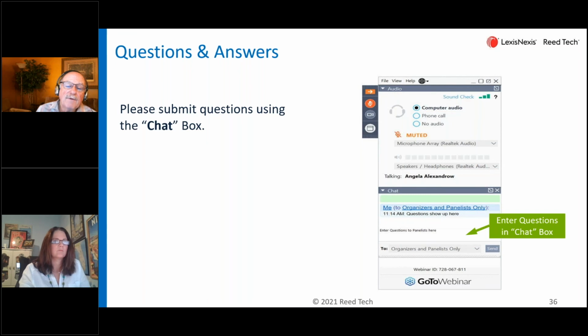Then I would recommend, as these legacy devices now have an equivalent device or a standalone, that you then transition to provide more and more of those records in place of the legacy ones. If I had an equivalent device that is now passed and qualified under MDR, then I can go ahead and register that device. That would preclude me from submitting my legacy device.